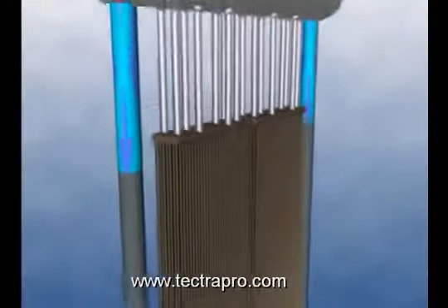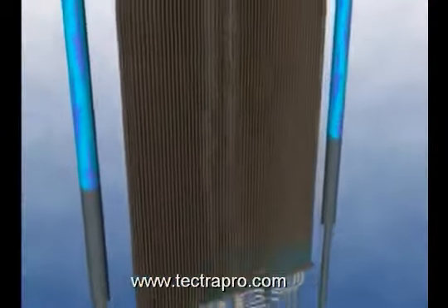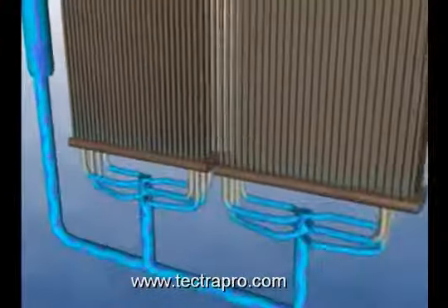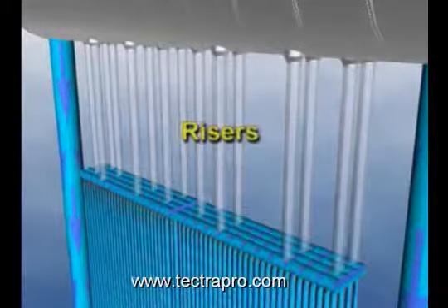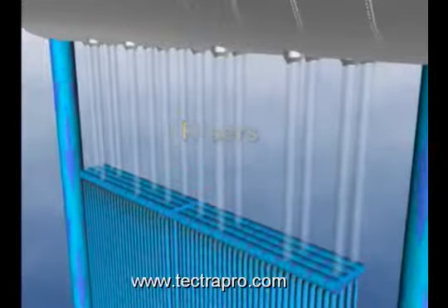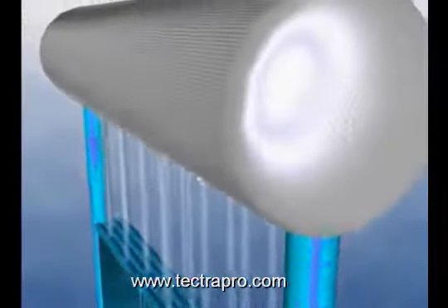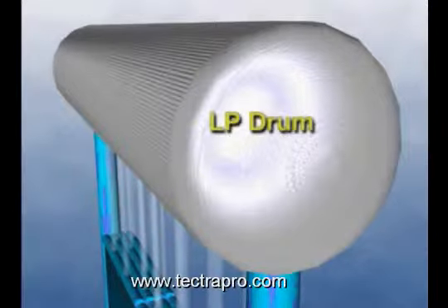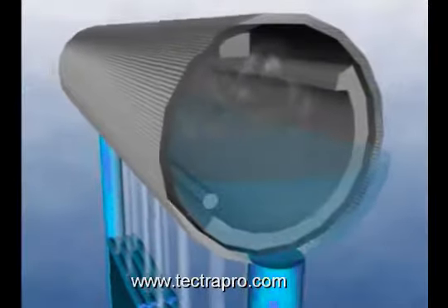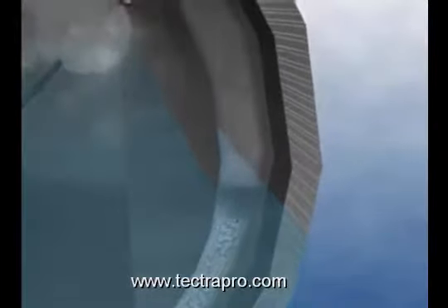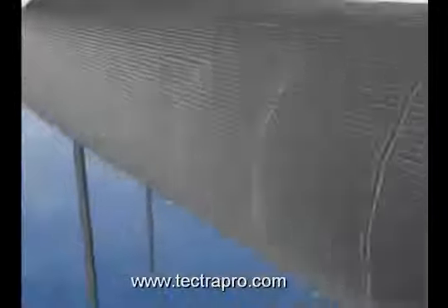Water flows out of the low-pressure steam drum through the LP evaporator and then back to the LP drum. Due to the difference in density between the water in the downcomers and the steam-water mixture in the evaporator and risers, the lighter steam-water mixture returns to the drum.